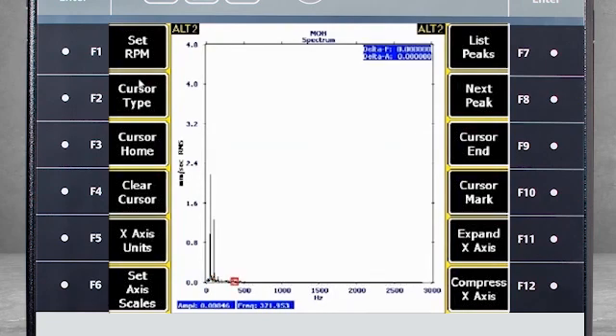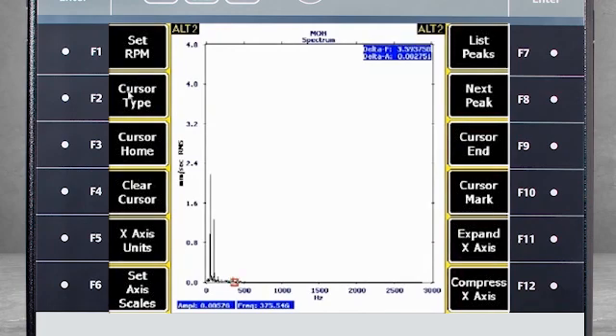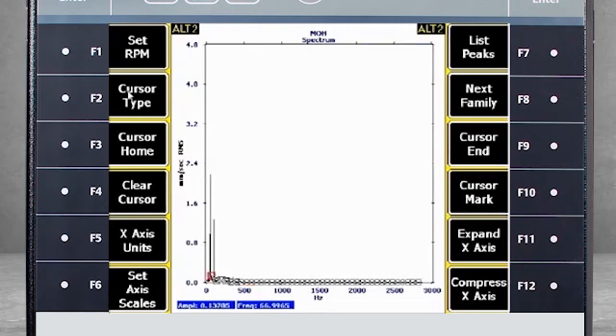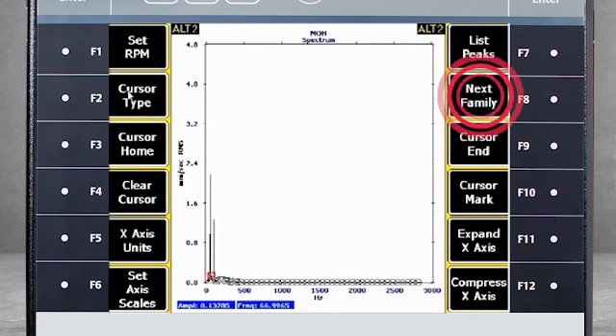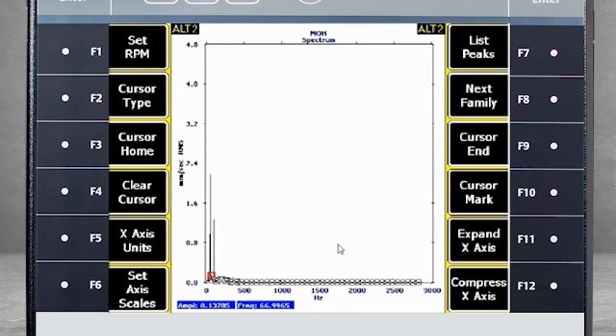Press F2 four times for sideband cursors shown here, and press F2 five times for harmonic families. You'll notice that your F8 key has now become your next family key. The analyzer will calculate for you where the harmonic and sideband families are in the spectrum. Pushing the next family key will take you through each family, but in our example we have only one family.